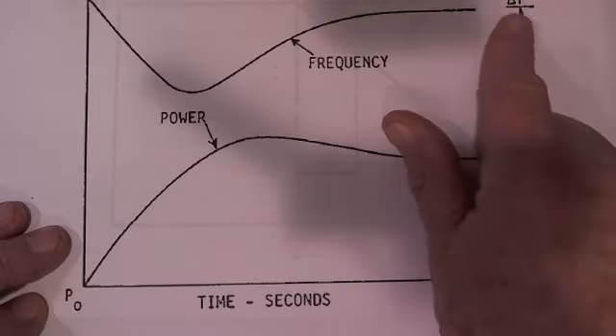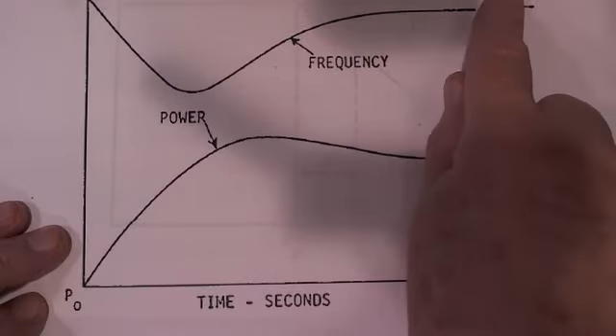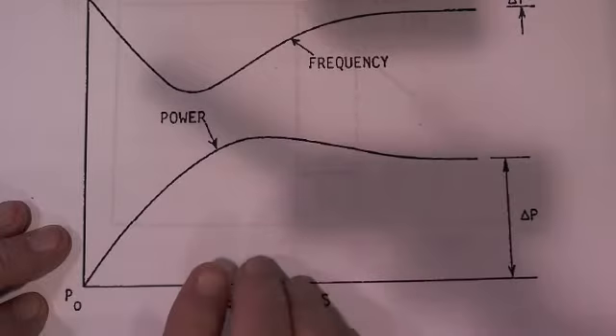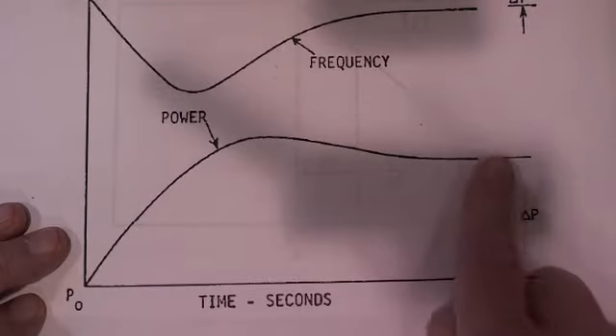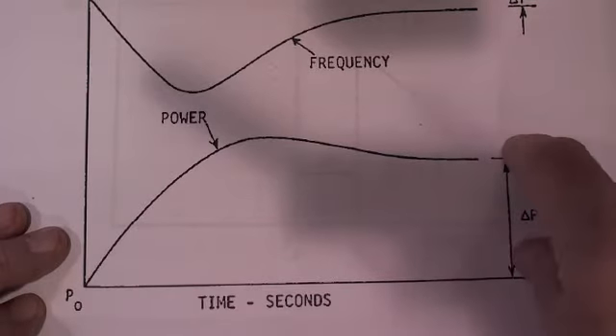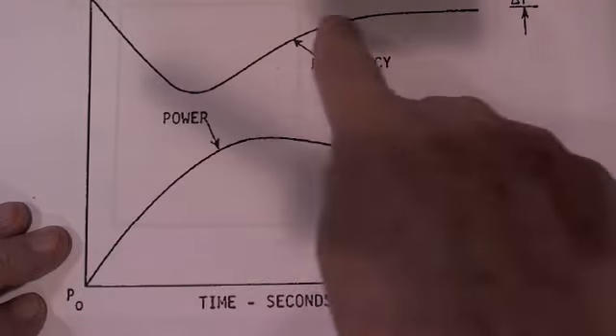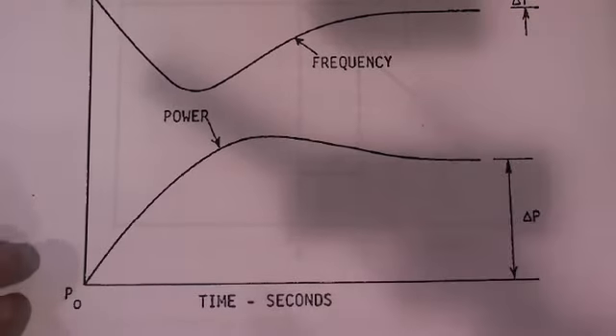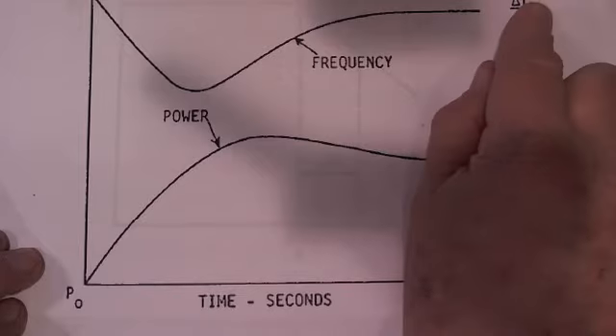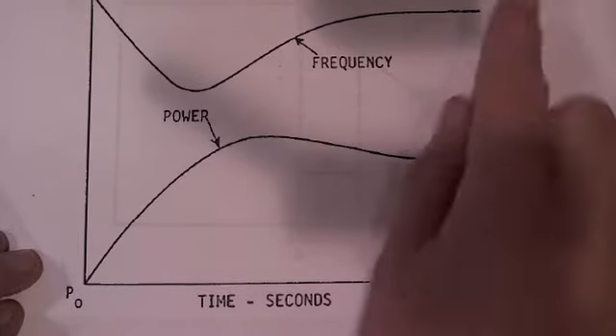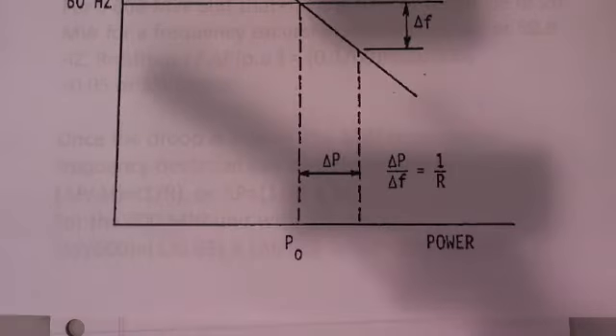and brings you back, but not to zero, not back to 60 hertz. And the frequency, so you get more power, the frequency goes down, comes back, and there's a slight deviation. We're going to talk, that's important to note. It does not reset it to zero yet.